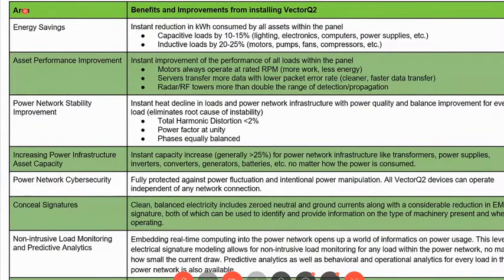But our whole contention is, when that event originally occurred, there was a delta in the electrical signature. And that delta has continued and continued until it can be detected. The wear and tear has occurred so much that it can be detected by ultrasonic. And then the wear and tear continues, and then it can be detected by vibration, and continues until it can be detected by heat, and then eventually it fails. So this method is a thumbprint on all predictive analytics and non-intrusive load monitoring going forward. And that's a huge advantage as well.